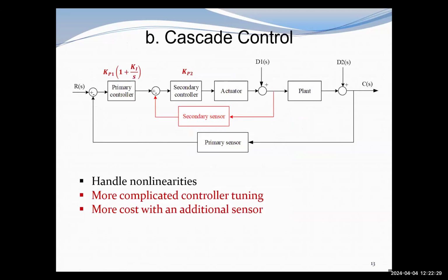For the cascade control, to design it, we add a secondary controller and a secondary sensor to create a secondary loop. Within the secondary loop, it will respond faster to eliminate the inner loop disturbance and also compensate the inner loop nonlinearities. And for this control strategy, we have to tune two controllers, the secondary controller and the primary controller. The controller tuning is more complicated, and also we need an additional sensor.